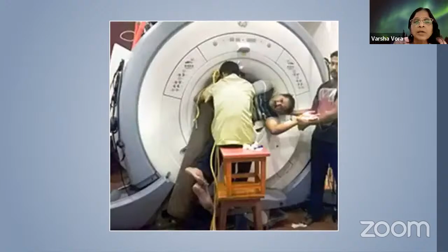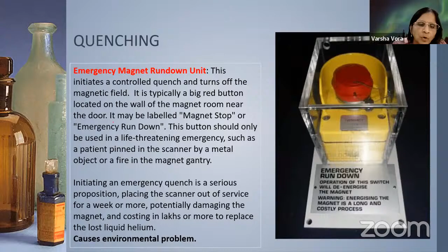Quenching is an emergency magnet rundown unit. This initiates a controlled quench and turns off the magnetic field. It is typically a big red button located on the wall of the magnet room near the door. It may be labeled magnet stop or emergency rundown. This button should only be used in a life-threatening emergency, such as a patient pinned in the scanner by a metal object, or a fire in the magnet room. Initiating an emergency quench is a serious proposition, placing the scanner out of service for a week or more, potentially damaging the magnet and costing lakhs or more to replace the lost liquid helium. And it causes an environmental problem also.